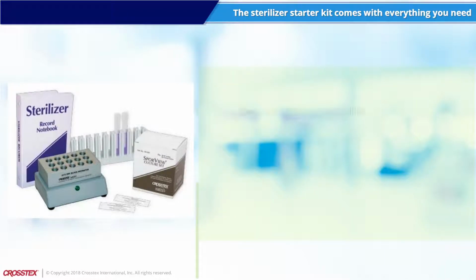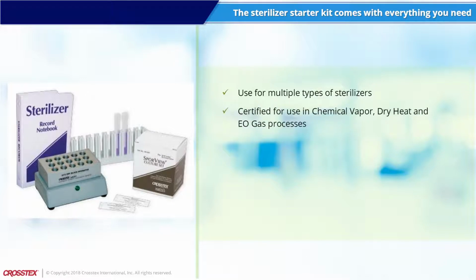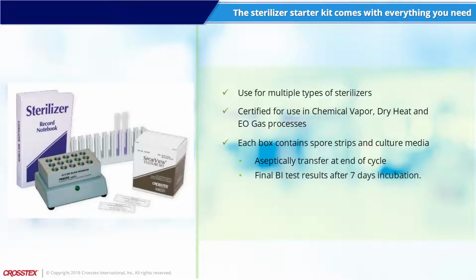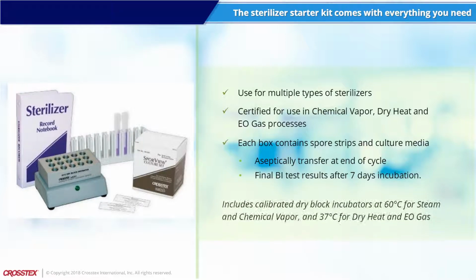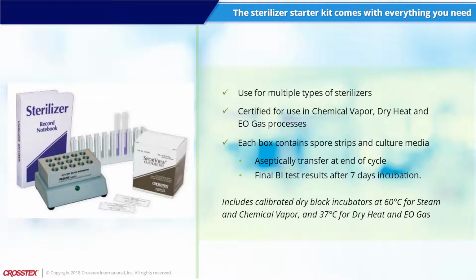The sterilizer starter kit comes with everything you need to conduct steam sterilizer testing. Product is ideal for customers with multiple types of sterilizers, as this product is also certified for use in chemical vapor, dry heat, and EO gas processes. Each box contains spore strips and culture media to be aseptically transferred for final BI test results after 7 days incubation. Includes calibrated dry block incubators at 60 degrees Celsius for steam and chemical vapor and 37 degrees Celsius for dry heat and EO gas.